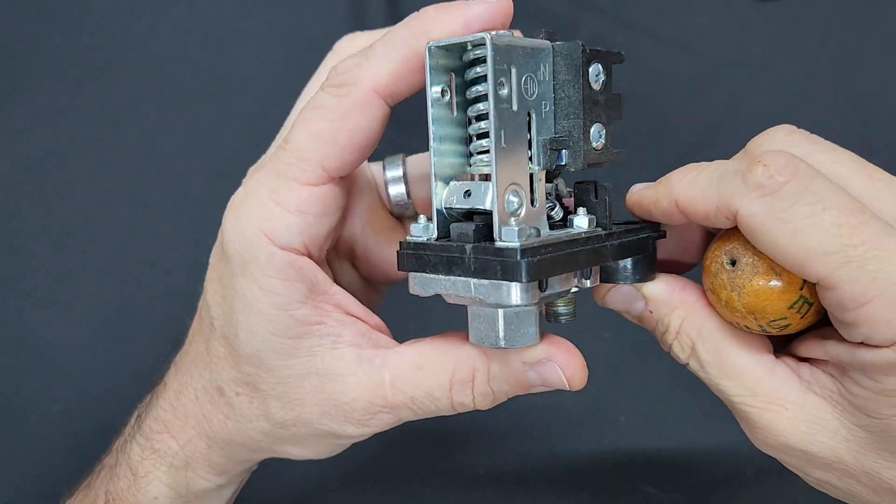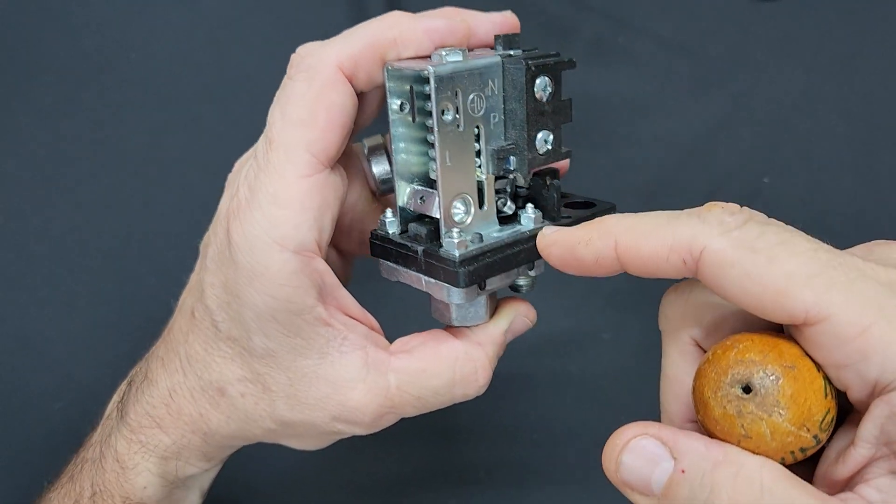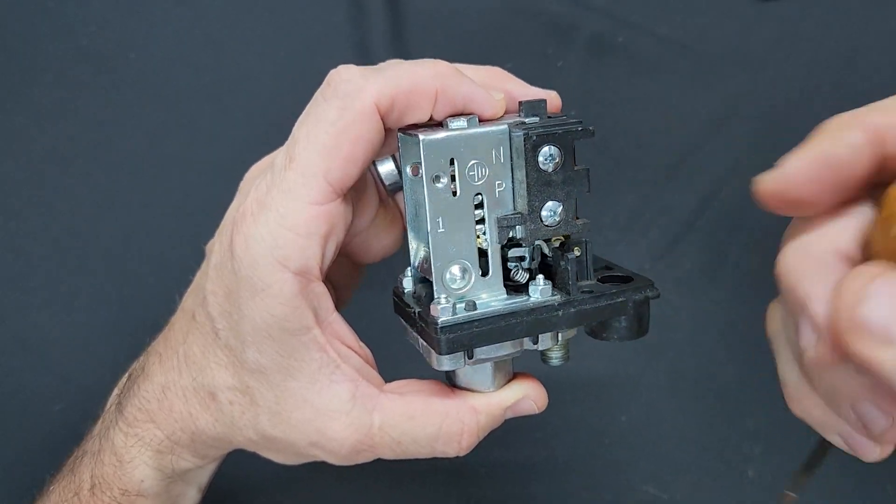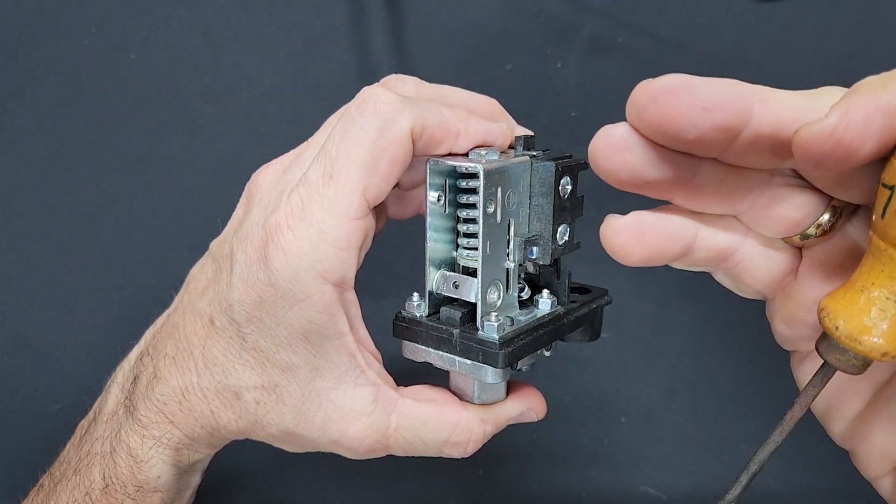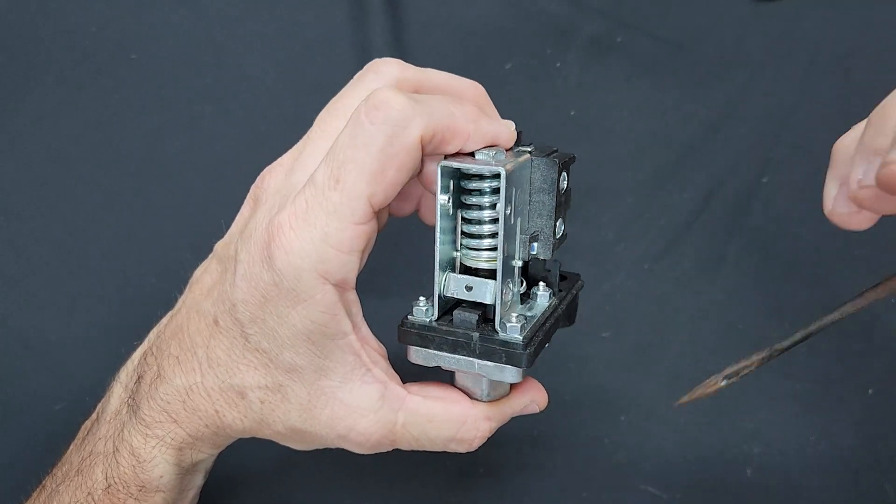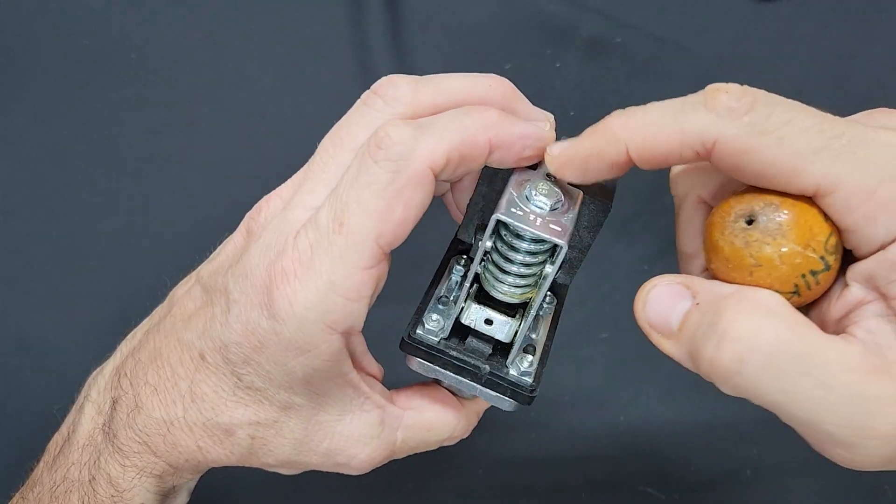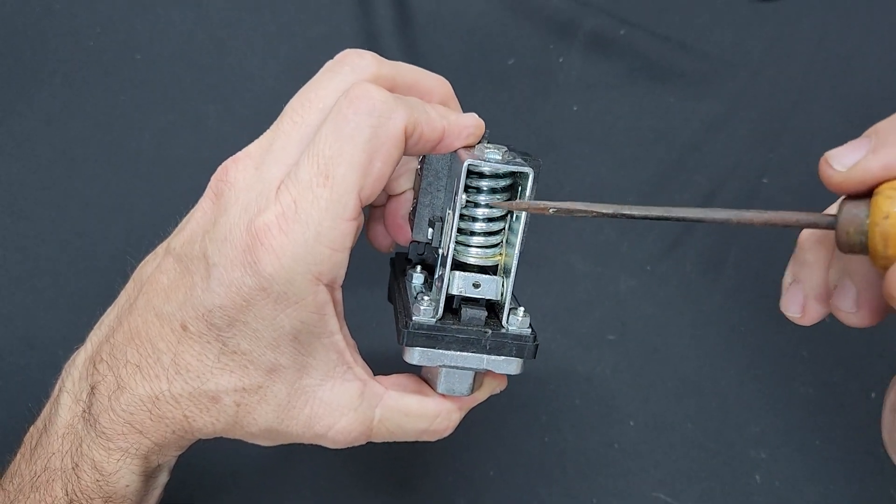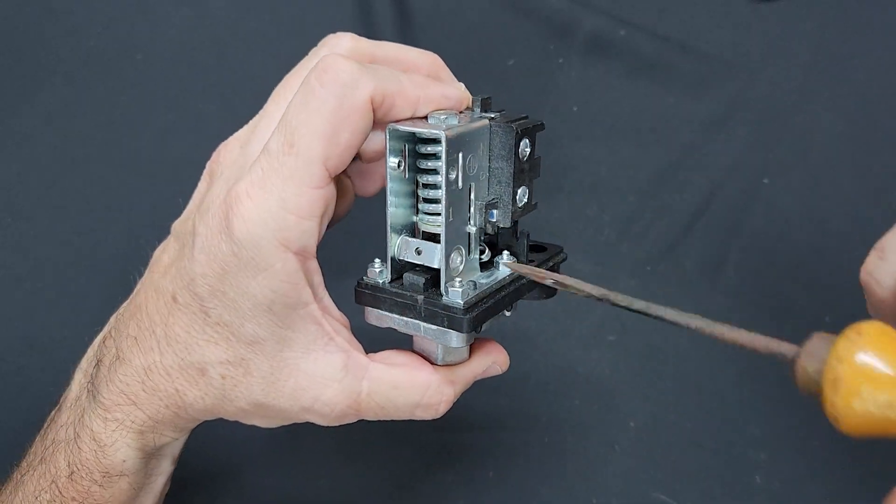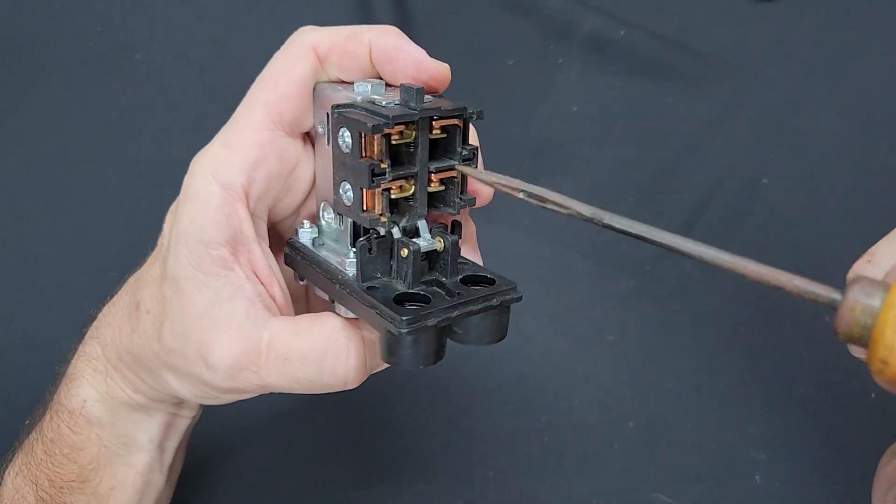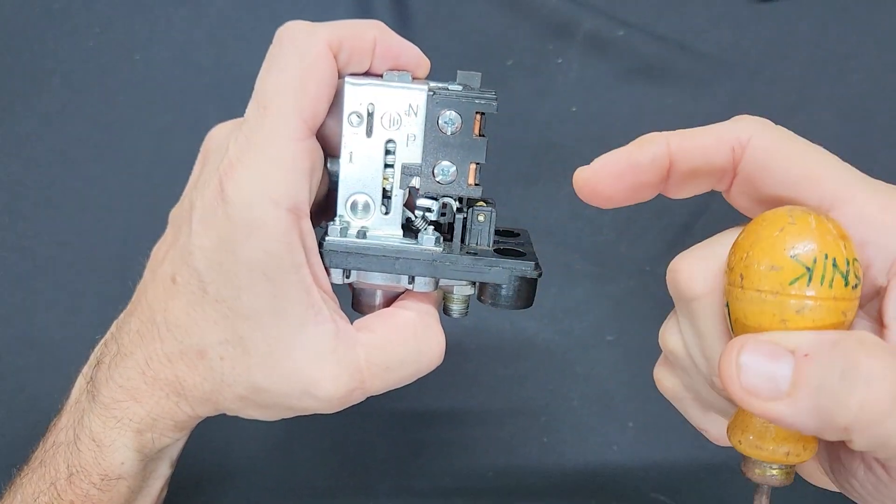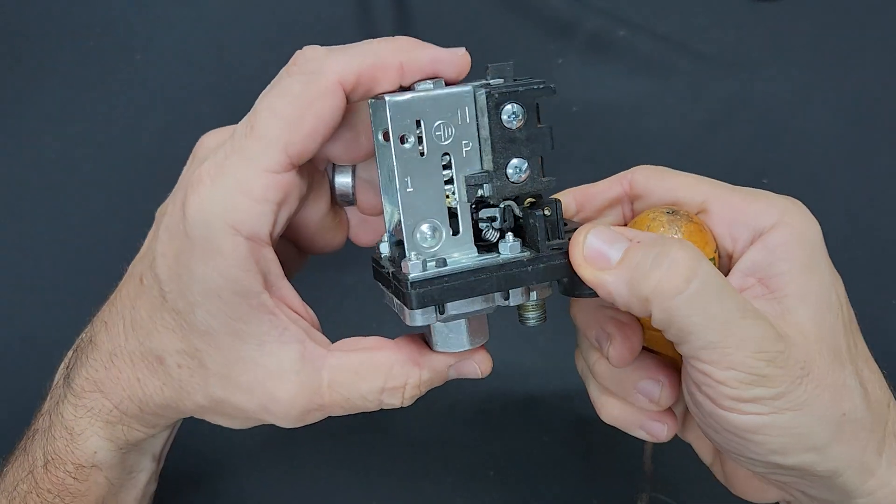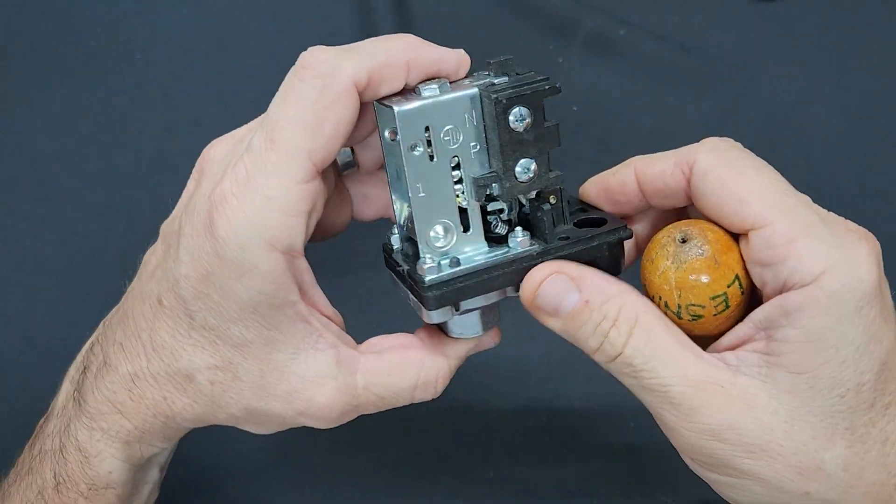then it's going to be opening up this spring making it a whole lot more looser, lowering the amount of psi in your tank and requiring the pressure switch to be activated a whole lot more often. If we want to increase the amount of pressure that is pumped into our tank we screw this clockwise, spring goes up, there's a whole lot more tension, and this switch will not actuate or will not turn on until there's a whole lot more pressure in the tank.